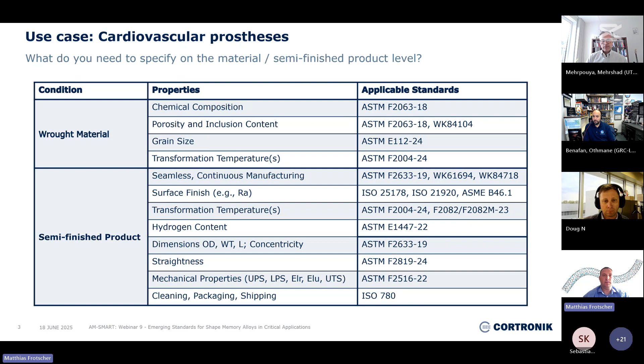When developing a medical device, like in this use case, a cardiovascular prosthesis, there are many device-specific standards which have to be applied for a successful submission to a notified body to eventually receive market approval. In the vascular interventions world, you can see that there is an ISO umbrella standard as an overarching guidance standard.